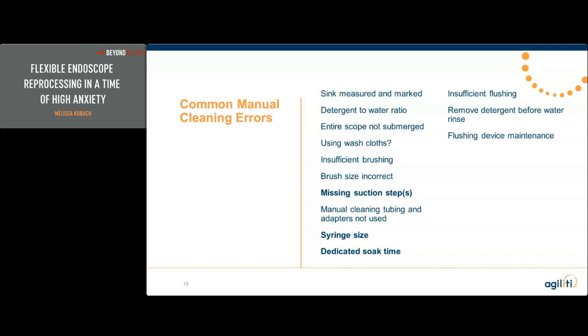That is when the minimum contact soak time per the chemical manufacturer starts. And I invariably have somebody say, but it's been in there all this time, and I understand that. But you really want the surfactants or the enzymes working on the trace elements, not the big elements, because there's always going to be some trace in these scopes at that point. You want it working on the things that you are not humanly capable of getting out, no matter how many times you clean it.